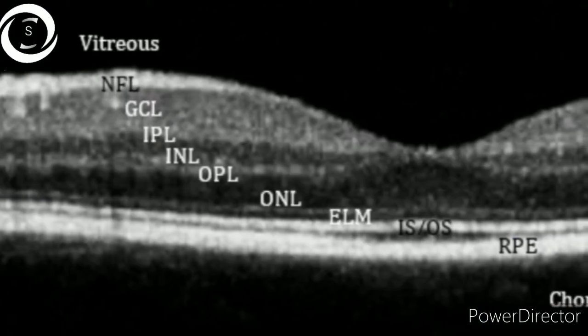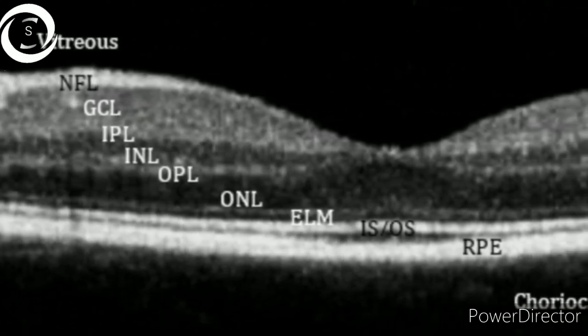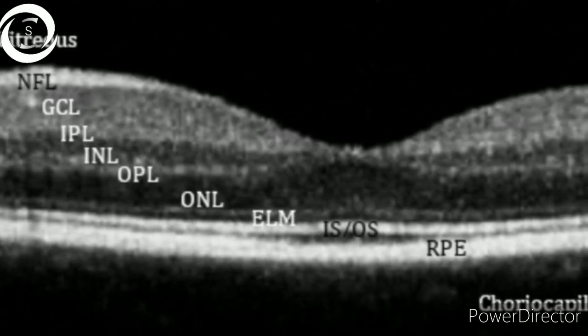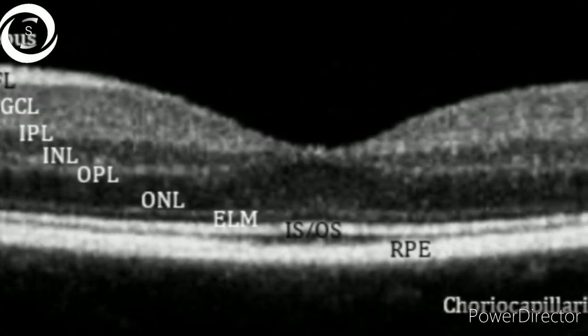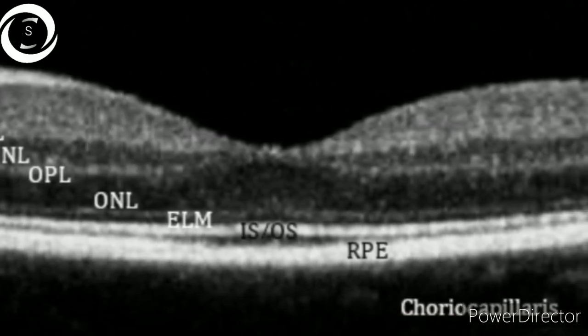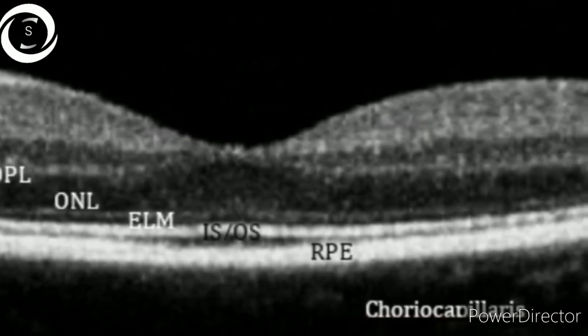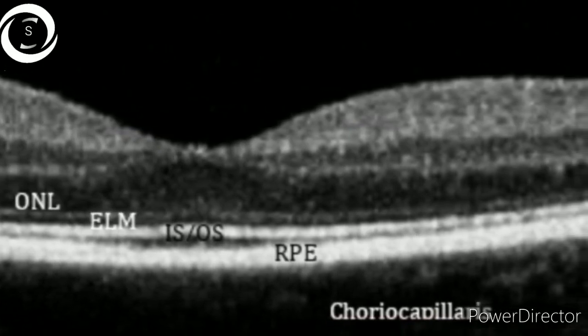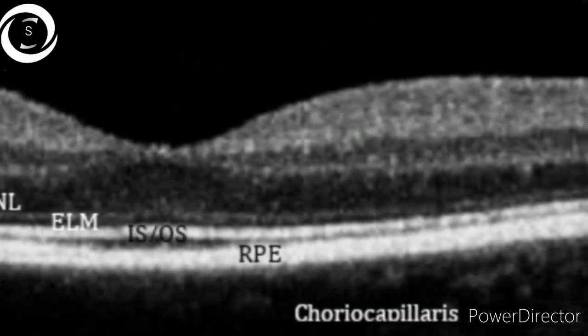Then came the spectral domain OCT, based on Fourier transformation of spectrometer analysis. Resolution was better — 5 to 8 microns — and a stationary reference mirror was used in Fourier technology. More than 20,000 A-scans per second were taken, usually in the range of 27,000 to 70,000 A-scans per second.